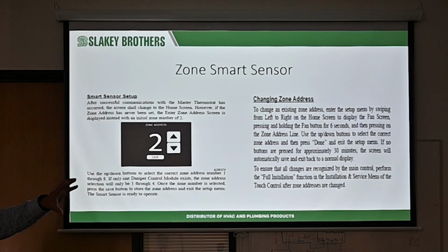So before you plug in that Connex, make sure your smart sensors are plugged in. Make sure you have them all addressed as I'm zone 2, I'm zone 3, or whatever it may be. If it's just an upstairs, downstairs, just 2 zones, you don't have to worry about it. Plug it in, you're ready to go. But if you have more than 2 zones, more than one smart sensor, make sure you're going in there and adjusting the zone for that smart sensor.